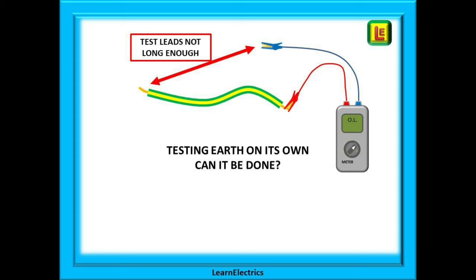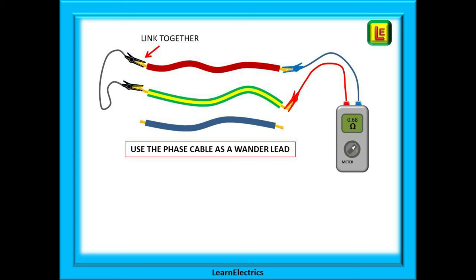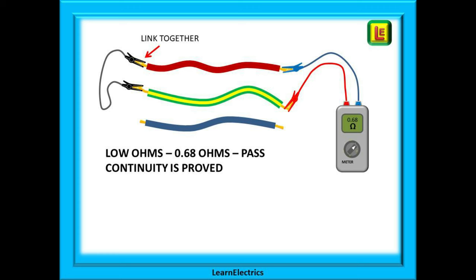The wiring regulations require us to test the continuity of the circuit protective conductors — the CPC — still affectionately called the earth cable by many electricians. But how can we test the earth cable on its own if the test leads will only reach a couple of meters and the two ends of the earth cable are at opposite ends of the house? Fortunately, most times we will be running a phase and neutral conductor to the same place as the earth conductor, so we can use one of these as a wander lead. We can link the far end of the phase and earth cable together with a connecting block, WAGOs, or as I prefer, short crocodile clips.